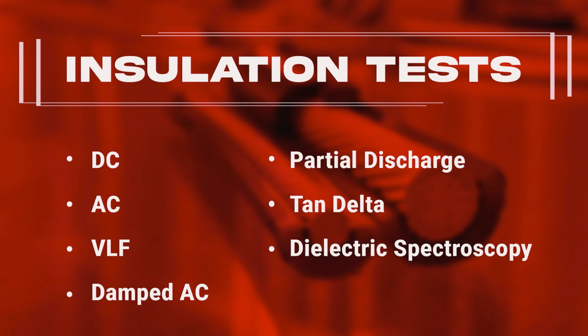But what a lot of people get hung up on is the testing of the main insulation system. There are a lot of options, whether it be DC, AC, VLF, damped AC, partial discharge, tan delta, dielectric spectroscopy. There's a lot out there, and it can be confusing. NETA's done a really great job of putting together recommended practices for the maintenance testing of cables, especially for what you'd say is the average cable.